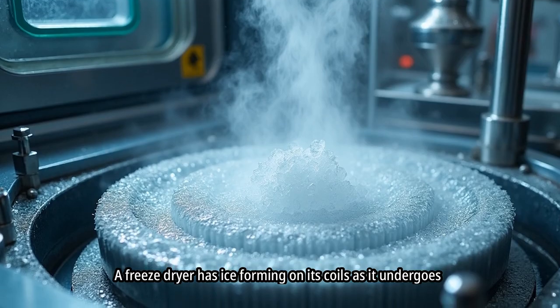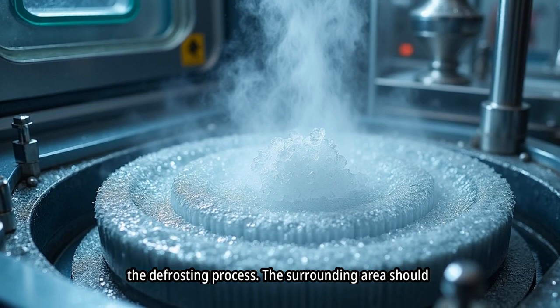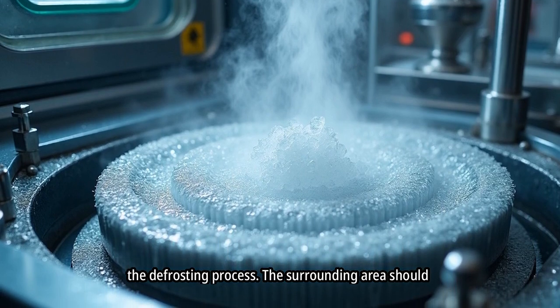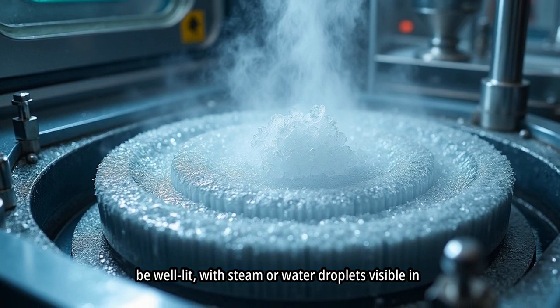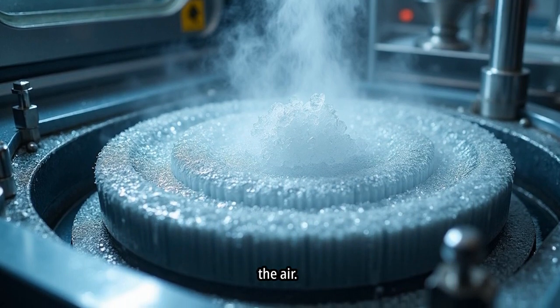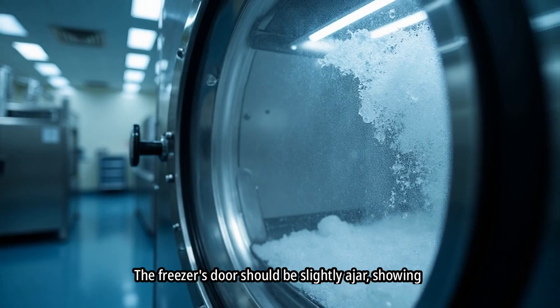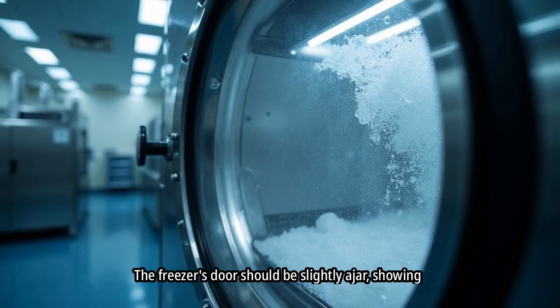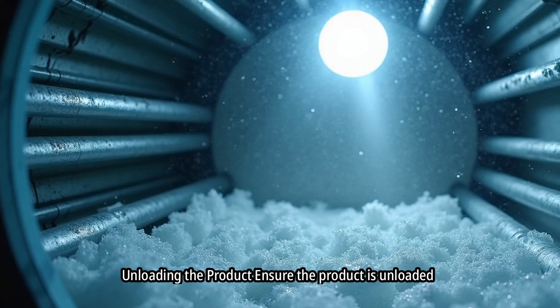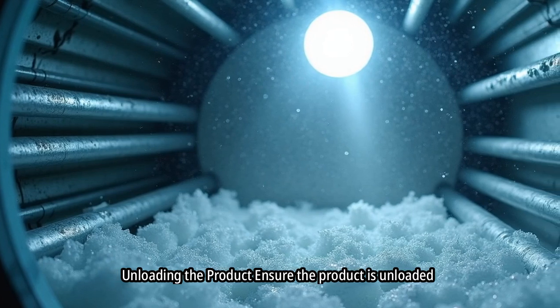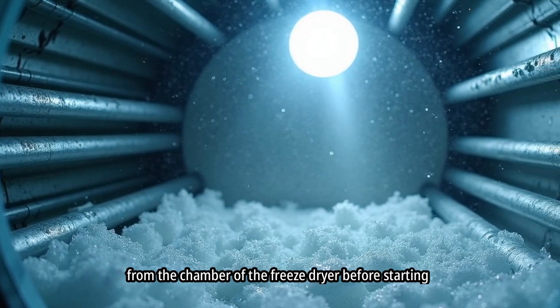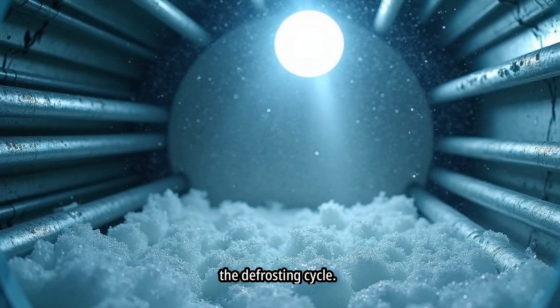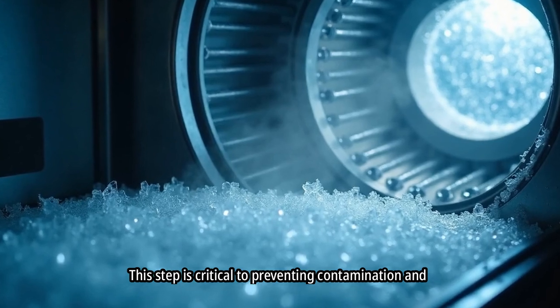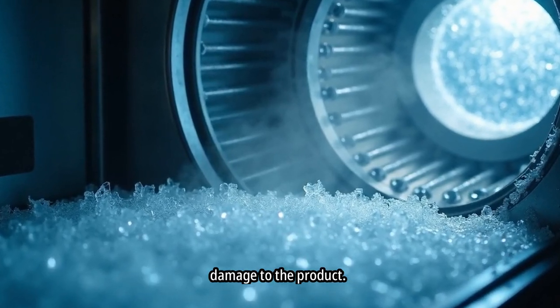A freeze dryer has ice forming on its coils as it undergoes the defrosting process. The surrounding area should be well lit, with steam or water droplets visible in the air. The freezer's door should be slightly ajar, showing the interior. Unloading the product: ensure the product is unloaded from the chamber of the freeze dryer before starting the defrosting cycle. This step is critical to preventing contamination and damage to the product.